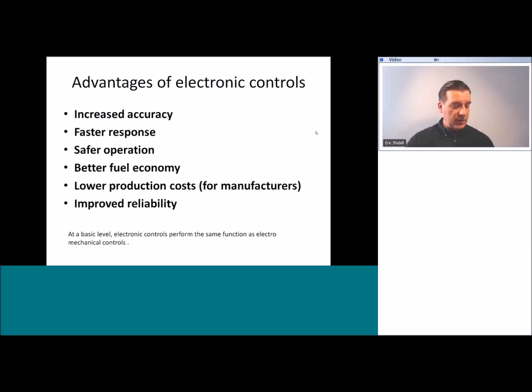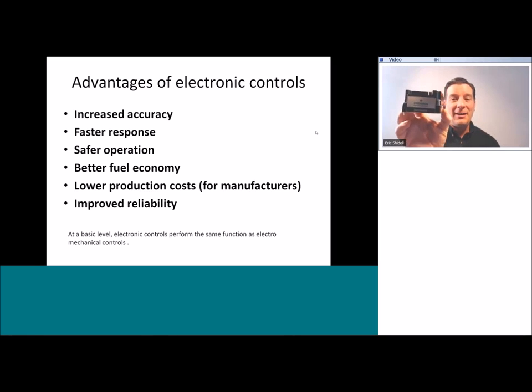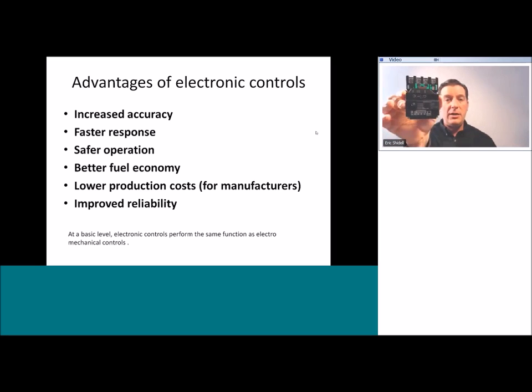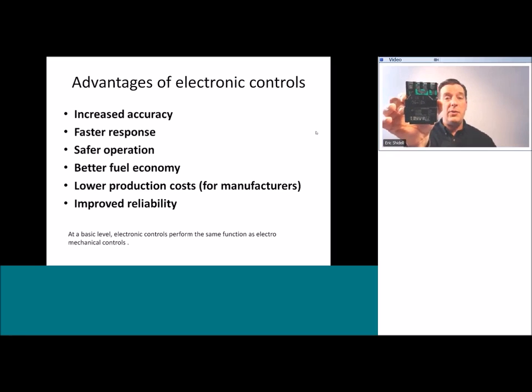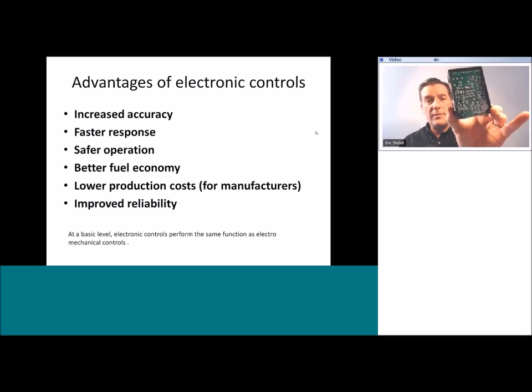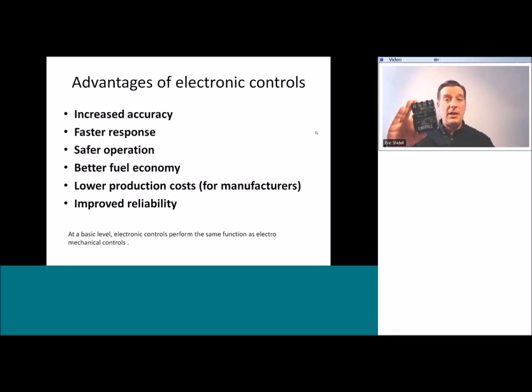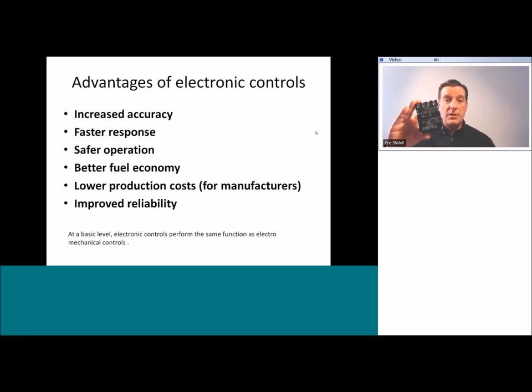To reinforce that idea, here is the Emerson Sure Switch contactor. This is a contactor for an air conditioning condensing unit — it could also be used in some refrigeration condensing units. It operates the compressor and the condenser fan motor. This is an electronic device that replaces traditional contactors. Here is its control board on the back side, and there's a microprocessor on here — some intelligence built in. The function of this device is virtually the same as a traditional contactor: it closes contacts to energize the compressor and condenser fan motor when there is a demand for cooling, responding to a 24-volt control input just like a standard contactor.